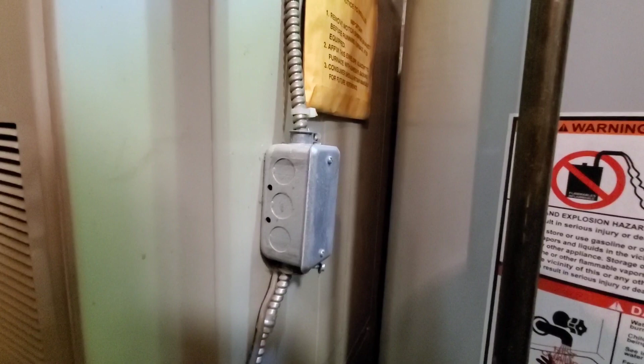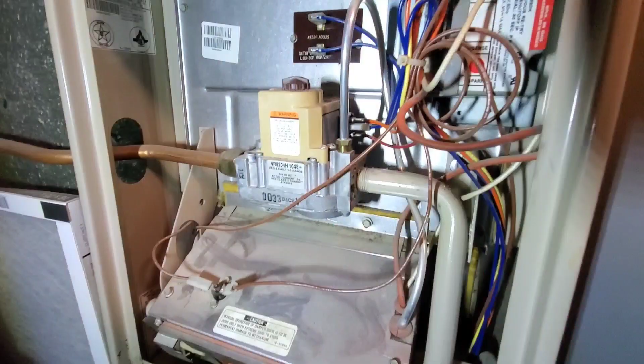And then this here, this is the thermostat wire. So this is the original wire here, and then this is the thermostat wire that they connected back into it. So the thermostat wire is 24 volts. This little one here is 24 volts, and then we have line 120 coming into the furnace. So what I'm going to show you now is the parts of this furnace.